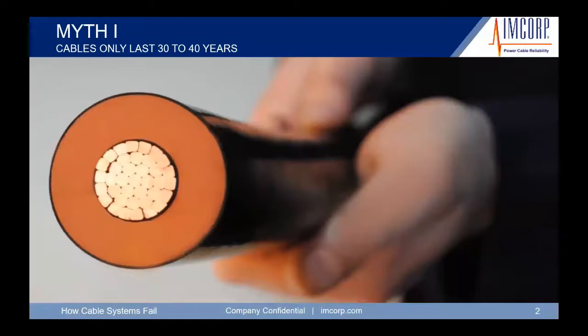On top of that, you can have a type of metallic shield. In the industrial market, we see the copper tape shield. Typically, in the renewable market or the utility, we have a concentric neutral type shield, and then an overall jacket. So a little bit more complex. But today, we see cables that we're testing in the field that are upwards of 50 years old, and if they're installed properly, maintained and protected, they're operating better than like-new cables.